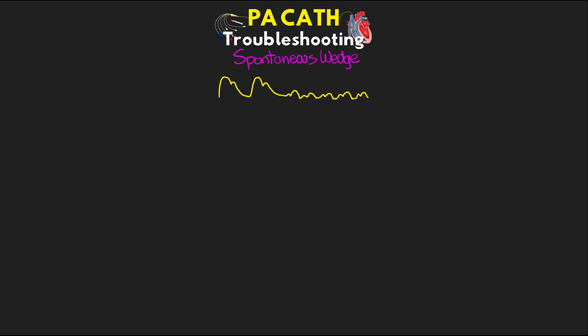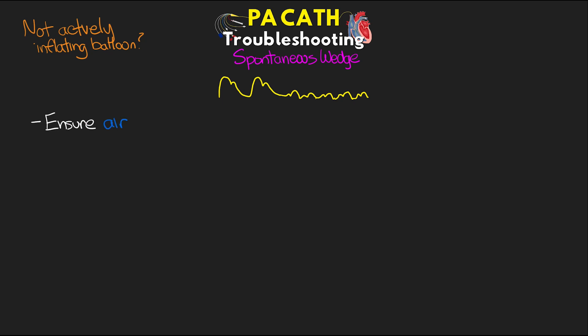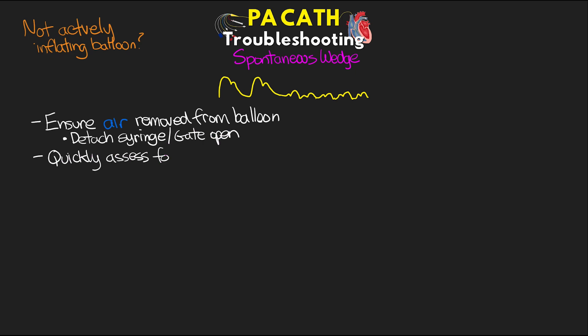Next is if we have a spontaneously wedged waveform. If you suddenly notice a wedge waveform and you're not actively inflating the balloon, then first you want to ensure that air is removed from the balloon — detach the syringe and make sure that the gate is open. Then quickly, you want to assess for any causes of a dampened waveform, which I'll cover in just a minute.